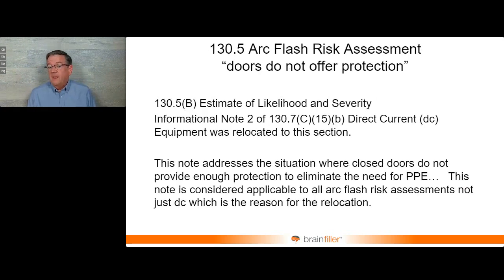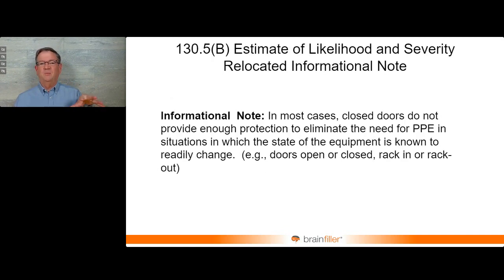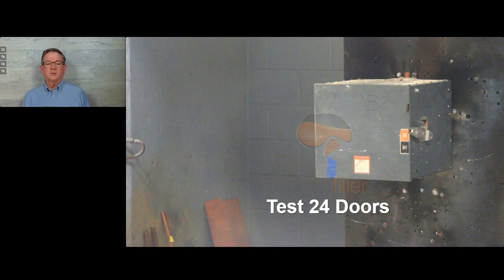The doors, it's somewhat known that doors may not offer protection in an arc flash. I've seen that a lot from a lot of my testing and arc flash work. But even though there was reference to the doors may not offering protection in 70E, it was in the wrong place. It was buried in language about the DC side of things. So we really need to pull that out and make it common for everything, that the doors don't necessarily offer protection. I mean, the doors might stay closed, but you never know. I have a couple of videos that I want to show you for this. This first one is some testing that I conducted a while ago. It's a small little bus plug, not that big. And well, let's take a look at it.